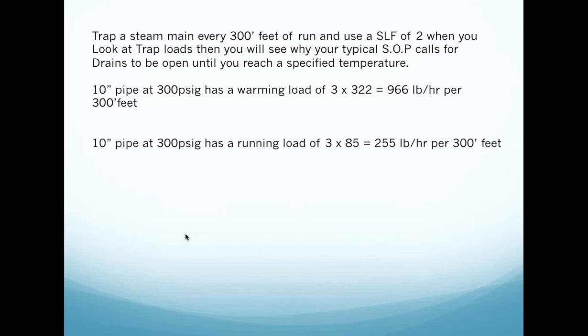Now, I have seen people that will say, well, Nick, I don't want to put a trap every 300 feet. I'll put one every 500 feet, every 800 feet. You know what? You can do whatever you want inside your facility, but I need you to know that when you turn that steam system on, you're going to generate condensate. So you just have to get ready, however you want to do it. You can put them every 500 feet, 300 feet, 800 feet. It's your choice. But I want you to stay safe, because I want you to know something.